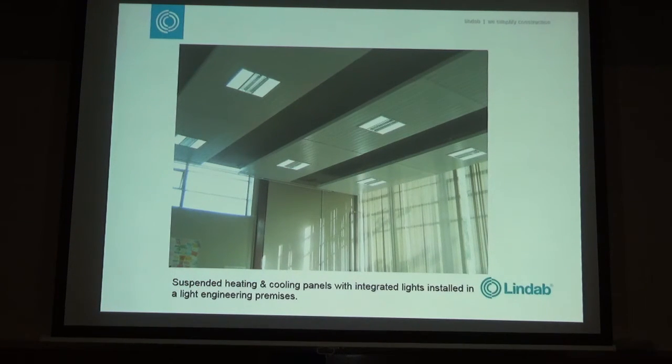Isn't that just a high-level convection again? Well, no, but what happens is it works like a displacement system does. If it convectively warms the floor up, and you've got a hotter area above at the ceiling height, you're reducing the temperature difference between the occupied zone and higher level. So it means that your hot air rises slower. It's like a displacement system. A displacement system works on the temperature difference. So if you heat up the ceiling, you reduce the temperature difference, and it means that the warm air and the warm surfaces don't lose the heat so quickly to the area of the panels.